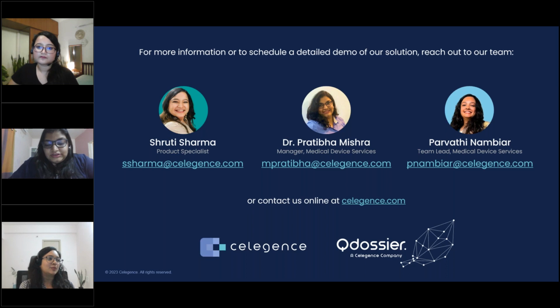Dr. Pratibha, if you have extra points. Yes, I have extra points about this question. I think if you start for any aspect, the starting point should be a good understanding of the intended use and indications. And guidelines are a good place to start, depending on the type of the device, for defining your acceptance criteria from state of the art. For some devices, it's pretty straightforward.